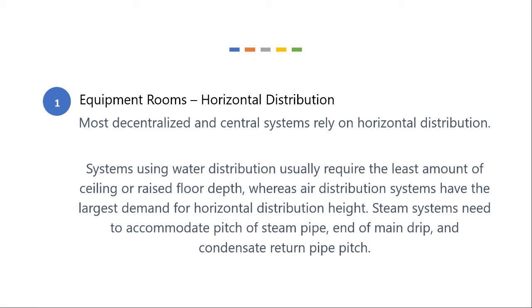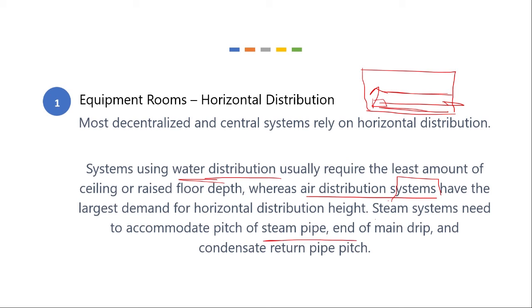So most systems that are decentralized have a horizontal distribution, and by that I mean you have a source, and the vents go this way, they don't go up and down. So if you're sending out water instead of air, you don't really need much because you just have a tiny water pipe. The water pipe might be in the floor or it might be in the ceiling, and you only need a few inches of space. If you're distributing air, then you need possibly a foot, possibly 2 feet. It's much more space required. If you're using steam, you need to be able to accommodate the pipe and the ends of the pipe.